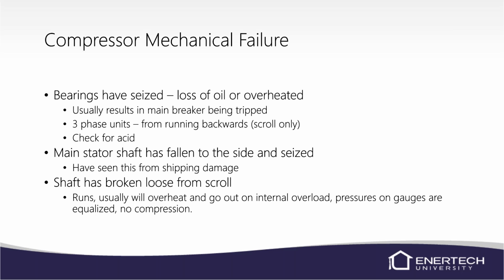When the bearing seizes, the breaker will normally trip, but it's going to pull that locked rotor amps. That's what's going to happen. 3-phase units are going to run backwards on a scroll. And if you've ever seen a compressor run backwards, you get really low pressures and low amp draws, it sounds crazy, and it's just not doing any work. It'll end up overheating. So on a 3-phase unit, make sure you've got your phases in balance. So make sure you're checking that.